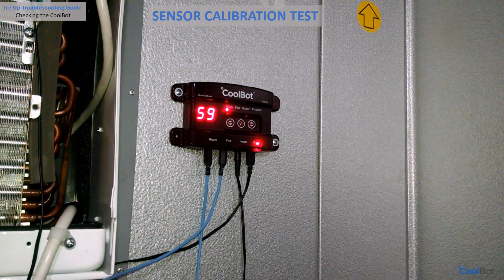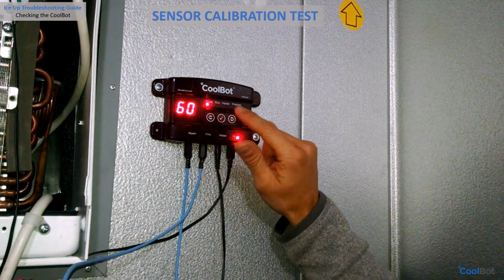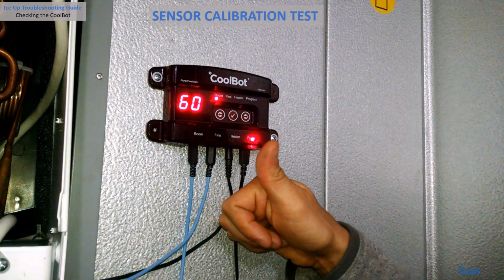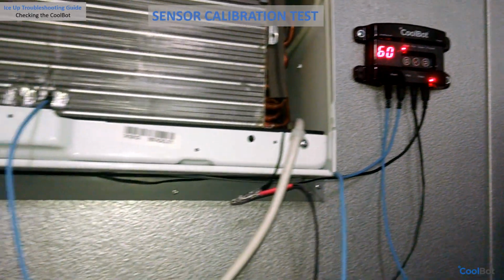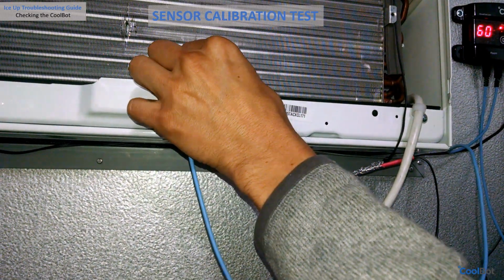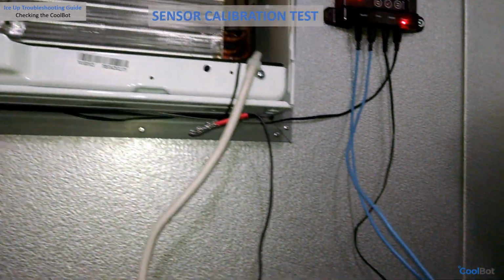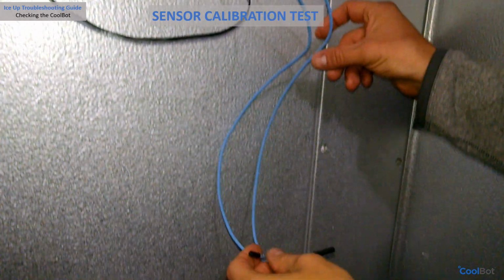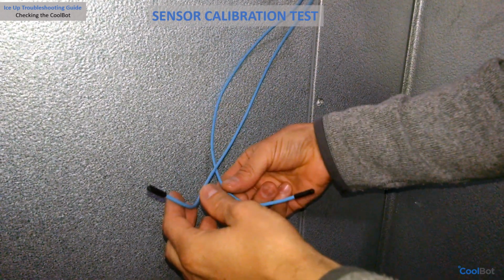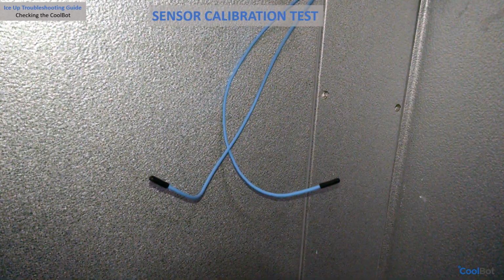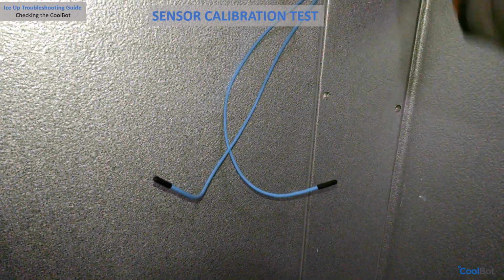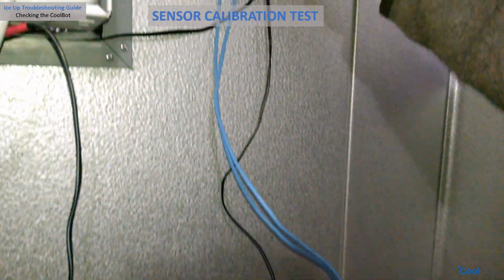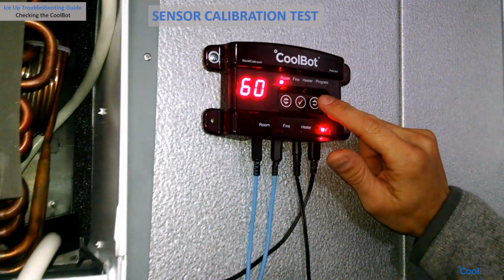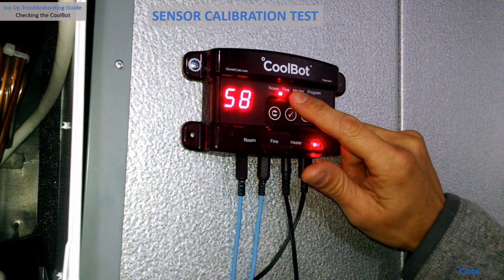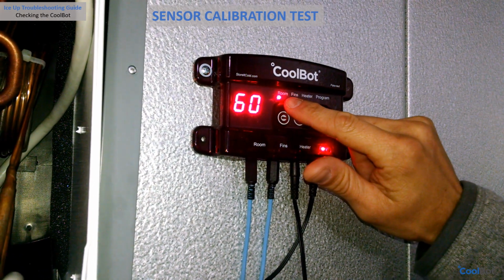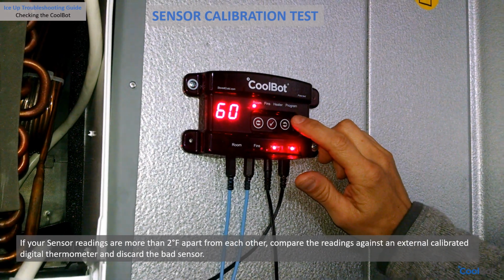If there are no errors showing on the CoolBot display, then let's do a last check for calibration of our sensors. Gently grab your fin sensor out of the front of the air conditioner and let it hang next to the room sensor. Toggle between room and fins with the arrows on your CoolBot and compare the temperatures reading on the display. Make sure the indicator light is either on room or fins as you toggle, and that you are not on heater or program.